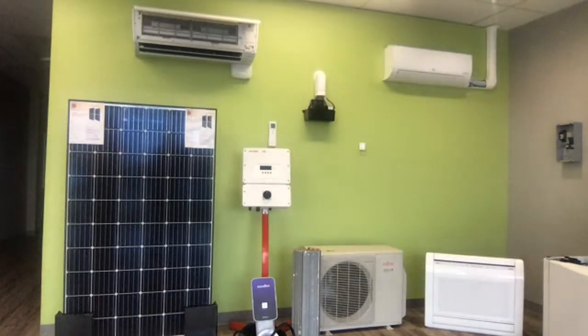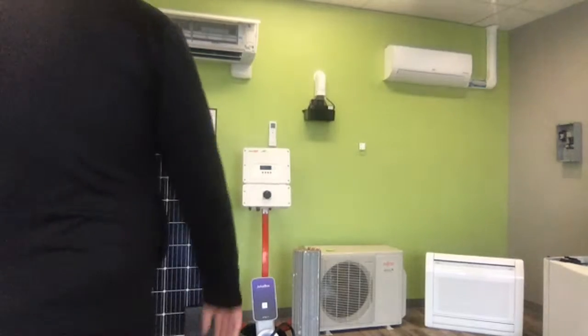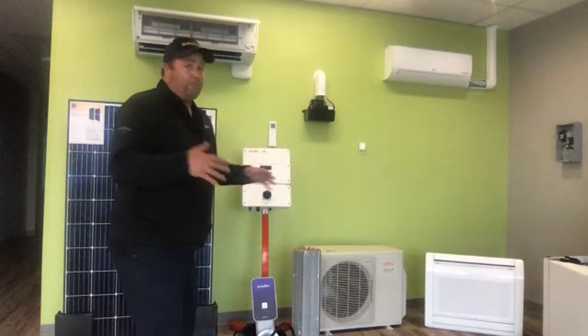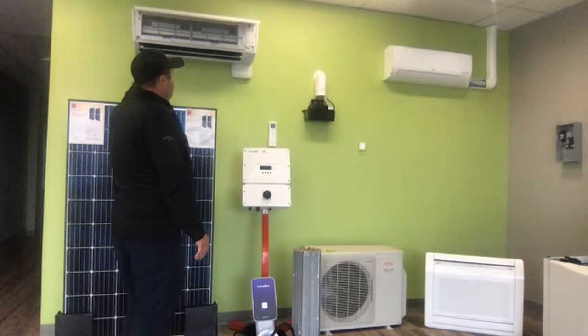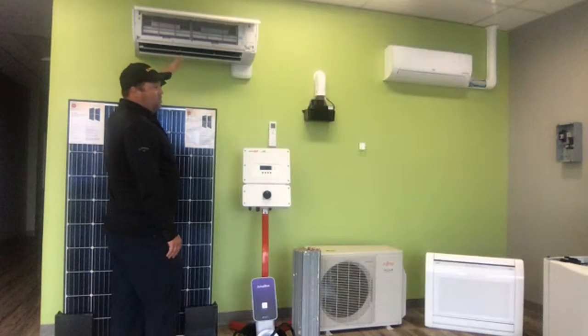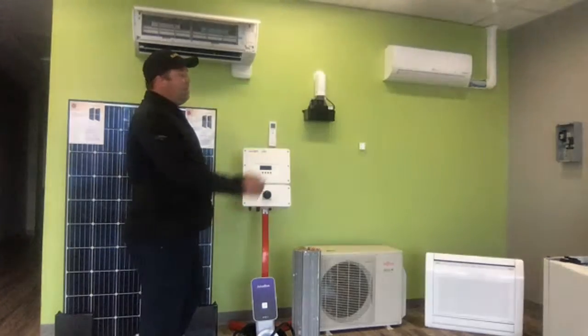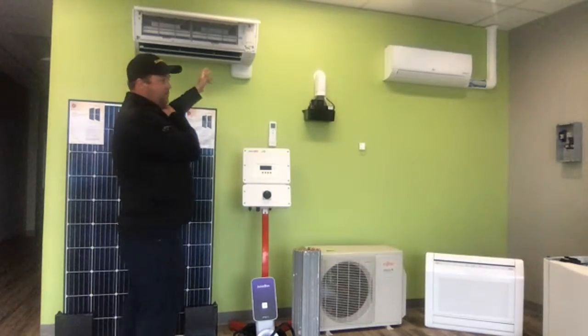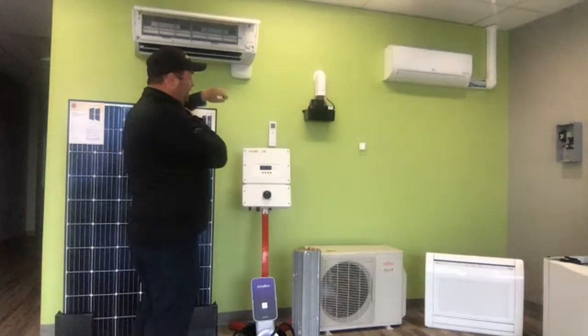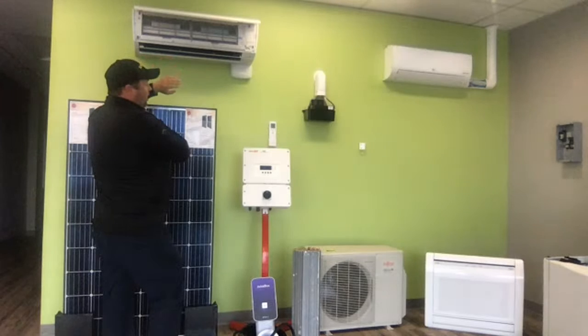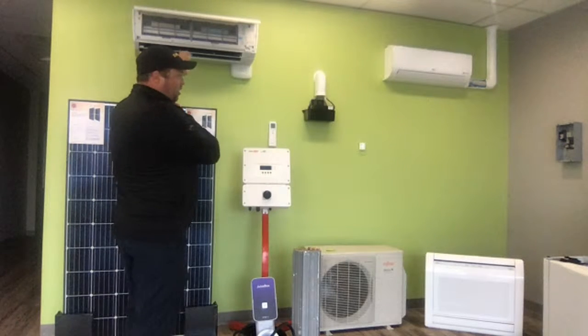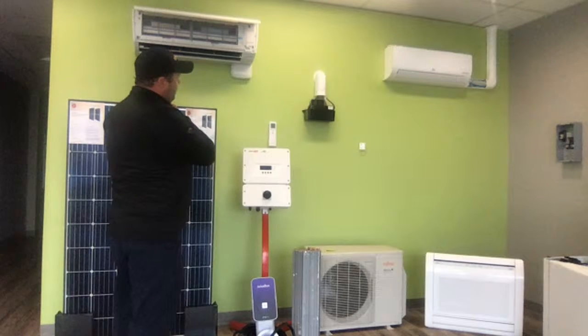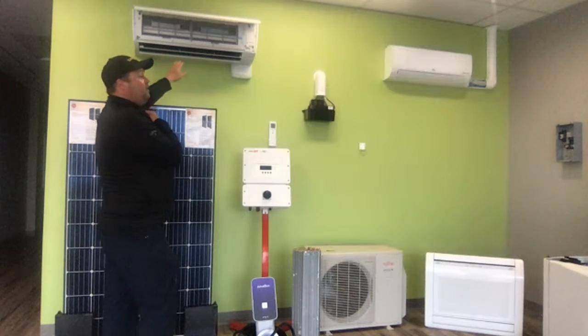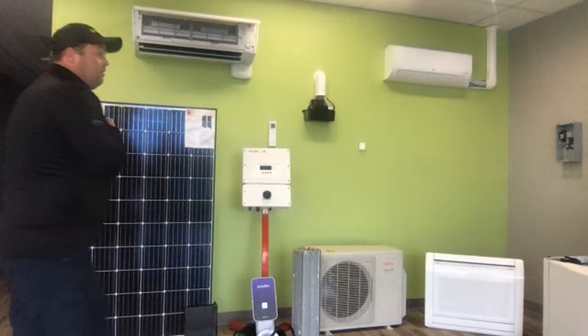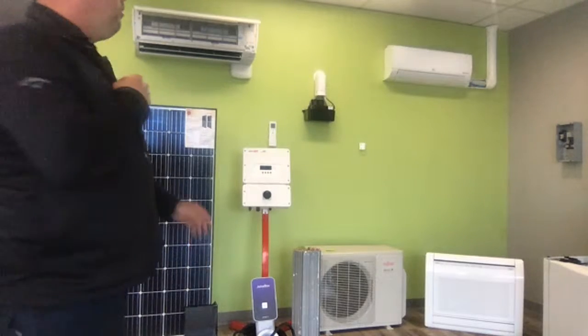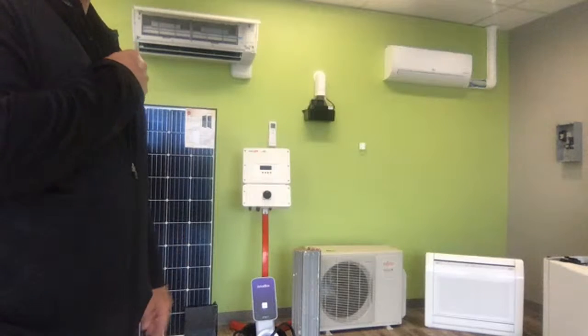Cost of a heat pump, 30 by 30. So sizing of a heat pump, roughly, just as a general rule of thumb, 9,000 BTU will do 600 to 800 square feet. A 12,000 BTU will do 800 to 1,000 in a Fujitsu. It's a little bit less with the LG. 800 to 1,000 feet, maybe even 1,100 with the 12. All right, and then anything above 12, you're looking at the 15, and then anything above 1,400 square feet roughly, you should be looking at a second heat pump.